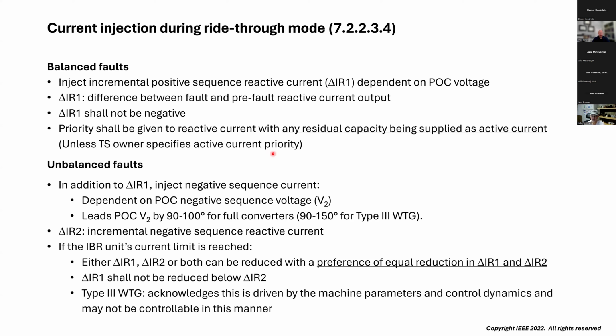Again, we'll see this show up in a couple different places, but any residual capacity, so any additional current carrying capability once you prioritize reactive current, needs to be active current. So use the full current carrying capability of the IBR unit. And that's, of course, if you're in a reactive current priority. If it's active current, then it'll be the reverse.